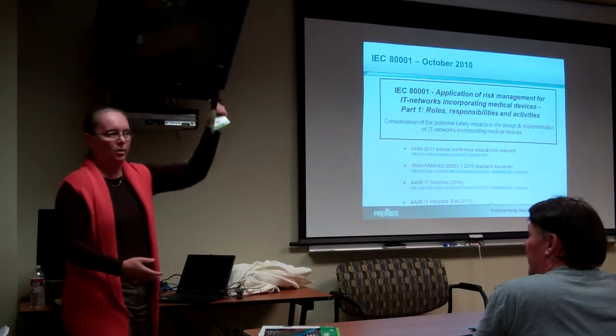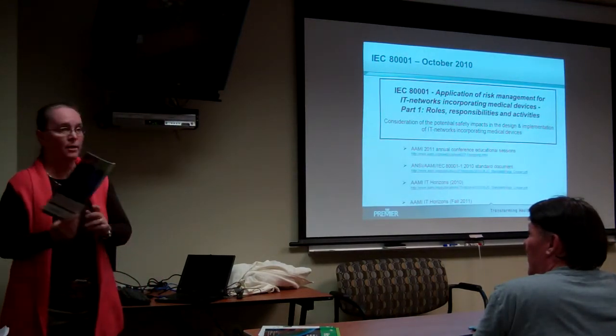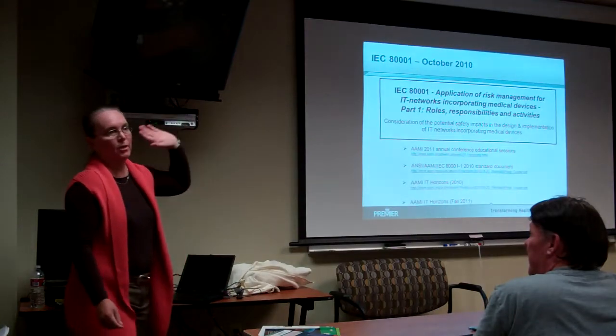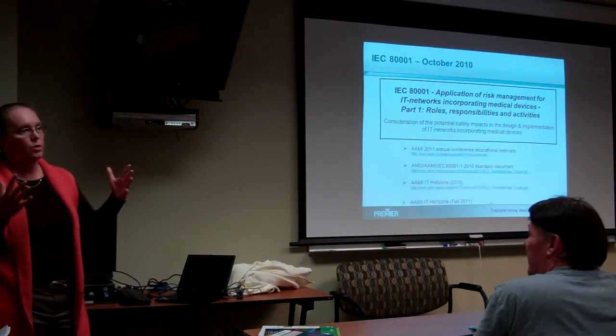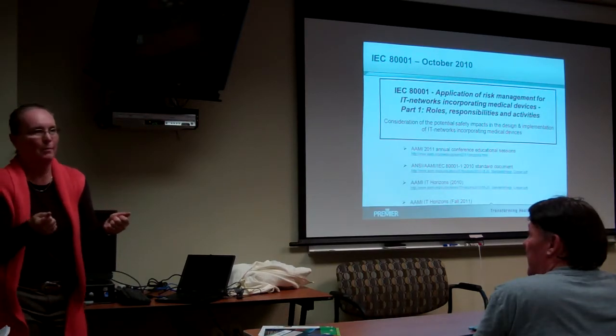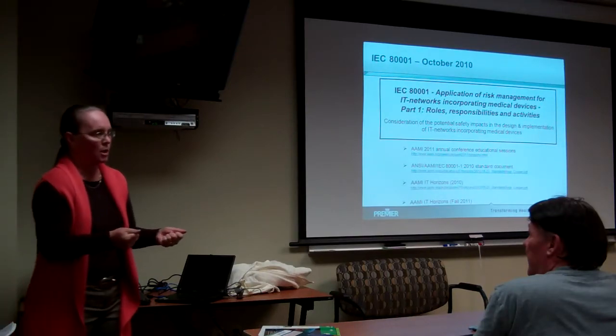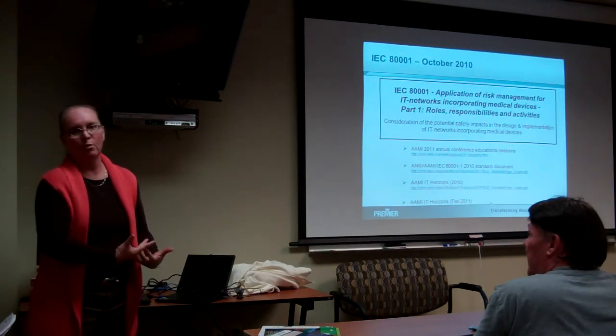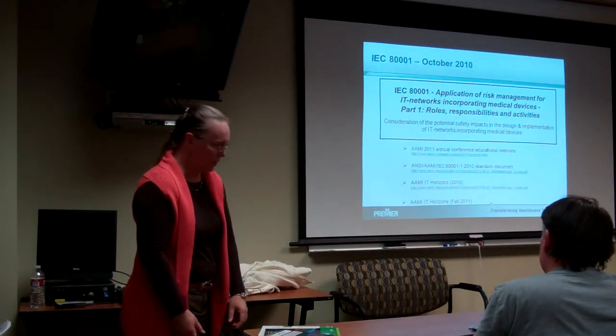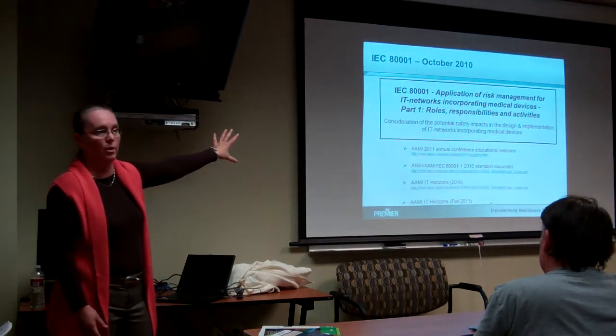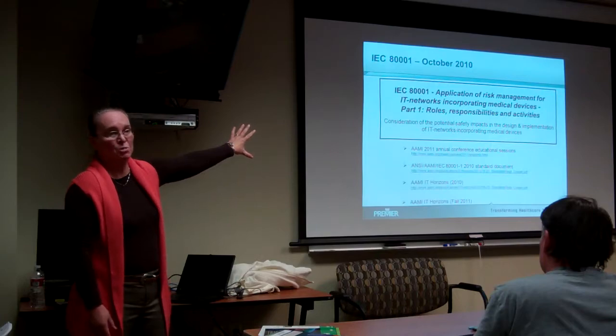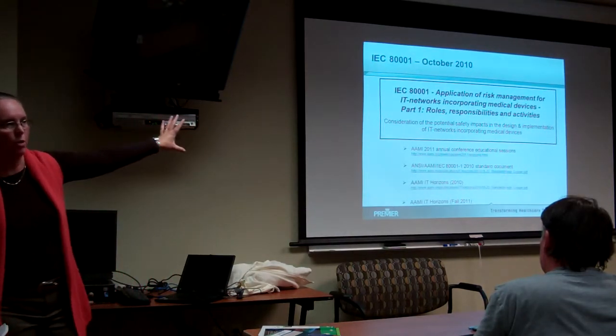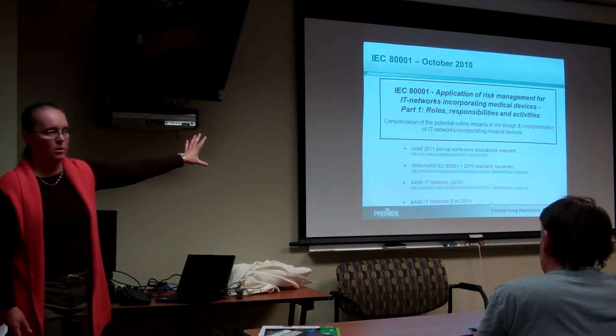Out in the hallway, there's an update on this: IEC 80001. There were a number of presentations at the AAMI conference this last June on this, and there's more information coming in terms of not just the standard, but also where's the instruction manual — how do I build this, and how do I manage it and use it? All these networks that are going to pop up and these interconnections are going to have to be managed, both technically and from a risk management perspective. This is a tool that you or somebody in your organization is going to need to become familiar with. This is a full-time job — not something that you give one of the techs in your department to sort of do when they're not doing PMs and running calls.